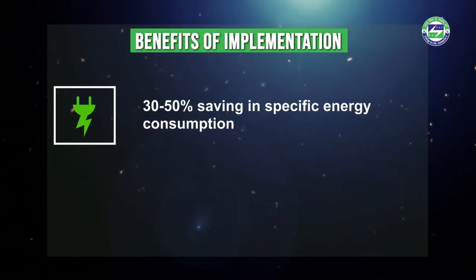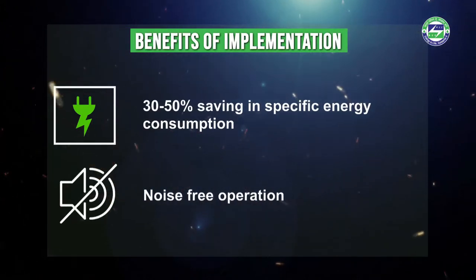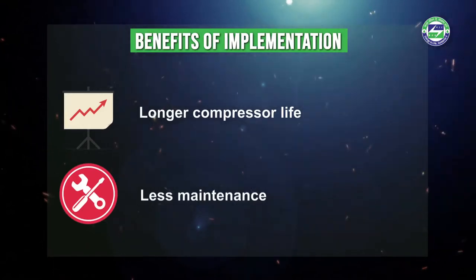Advantages of the screw compressor with VFD and directly coupled energy-efficient motor include 30 to 50 percent reduction in specific energy consumption, noise-free operation, longer compressor life, and less maintenance. This screw compressor technology can start and stop very easily, so no heat is generated inside, resulting in savings in heat energy and power energy of about 30 percent.